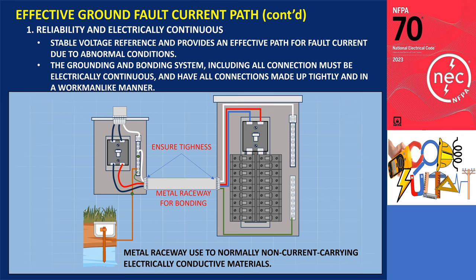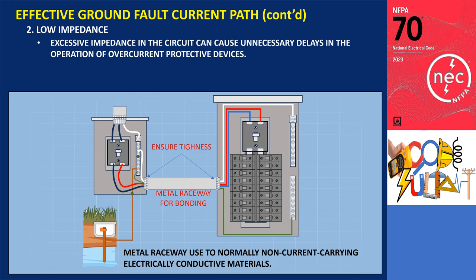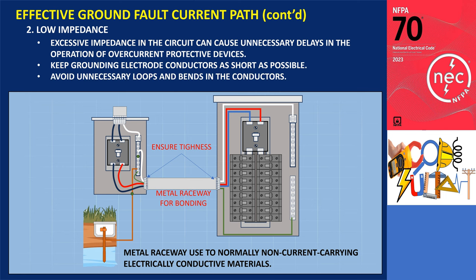A low-impedance circuit is characterized by minimal impedance achieved through proper installation techniques. Excessive impedance can cause unnecessary delays in the operation of overcurrent protective devices, compromising safety. To effectively limit voltage to ground, it is essential to keep grounding electrode conductors as short as possible, avoiding unnecessary loops and bends that can introduce additional impedance. By minimizing the length and complexity of the grounding electrode conductors, the voltage to ground can be effectively controlled, enhancing overall safety and reliability.